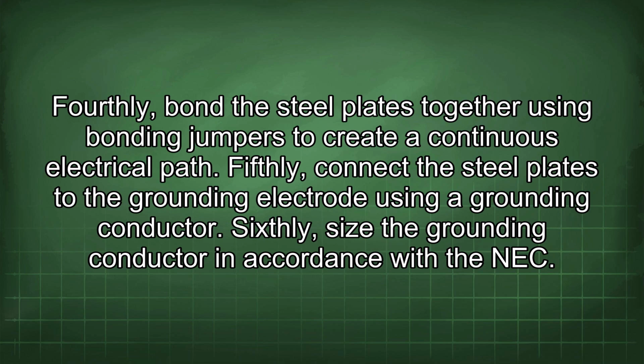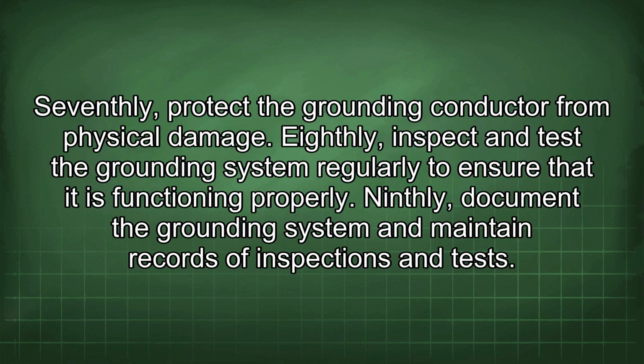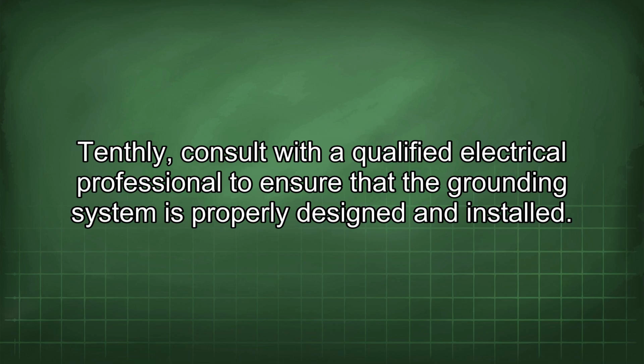Fifthly, connect the steel plates to the grounding electrode using a grounding conductor. Sixthly, size the grounding conductor in accordance with the NEC. Seventhly, protect the grounding conductor from physical damage. Eighthly, inspect and test the grounding system regularly to ensure that it is functioning properly. Ninthly, document the grounding system and maintain records of inspections and tests. Tenthly, consult with a qualified electrical professional to ensure that the grounding system is properly designed and installed.